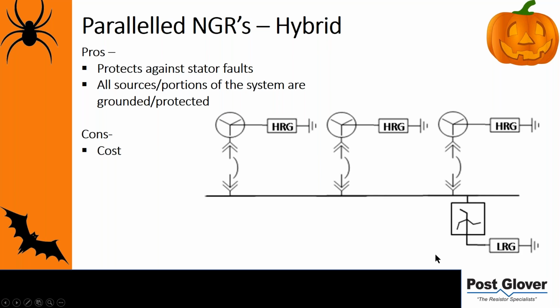Well, so this does a lot of different things. First, just like the first one, no matter what happens, you have some kind of ground protection. You never have an ungrounded system or anything like that. Another thing is this could potentially protect against stator faults in your generator. What I go into in my other webinar, in a nutshell, is if you have differential relaying across that generator and you figure out that there is a fault within the generator itself, you can open that generator breaker and wind down with just, let's say, 5 amps of ground fault, which is going to be saving your generator from extra damage. Obviously, solid ground would be horrible, but low resistance ground would probably, based on different papers, also cause additional damage.